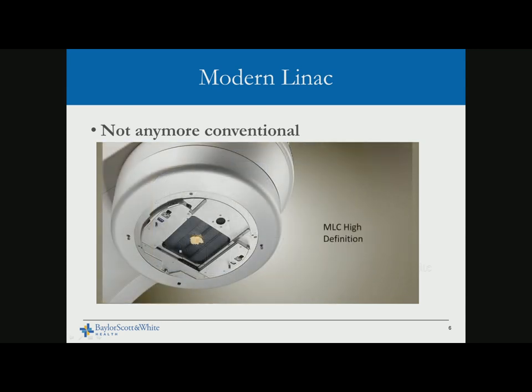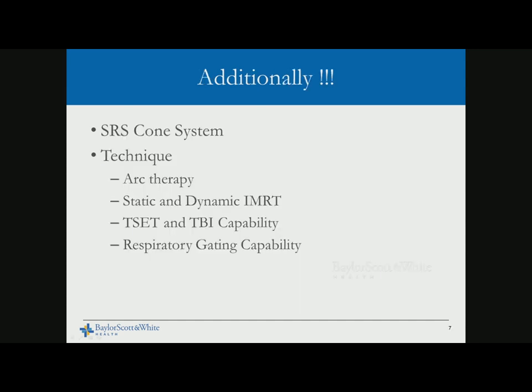If you have a radiosurgery system with a cone system, we need to be able to accept that. There is also technique-specific acceptance testing: if the vendor promises the LINAC can deliver a certain technology, we need to verify that at acceptance testing. Most of these tests are currently done in a functional way because no dosimetric data is collected and the planning system is not ready to assess dosimetric validity during acceptance testing.